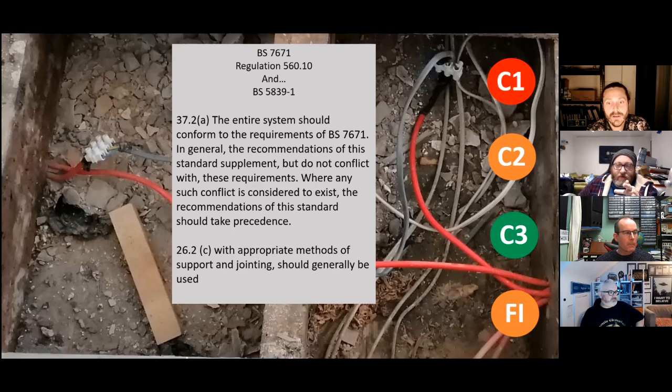Right. So fundamentally, the electrician needs to have that extra understanding of who else is going to raise this concern. If the fire maintainer is not going to discover it with regular testing, then I have to, right now, understand how to address that. And also, that's the purpose of the red cable. So we know that it's a life safety system. So even someone with little knowledge can look at that and go, that's a problem. The way it's been jointed is a problem.